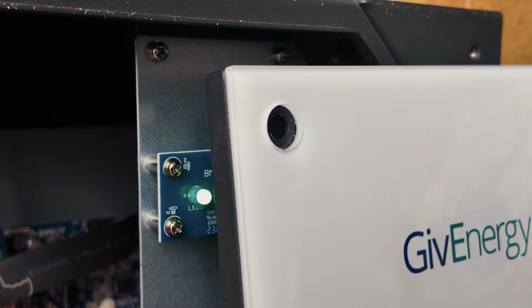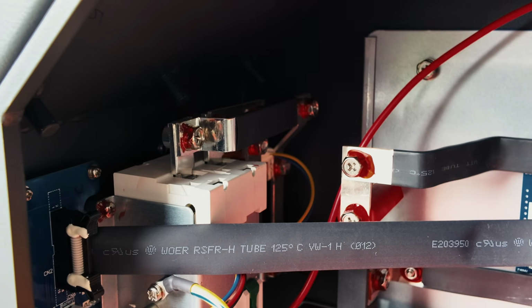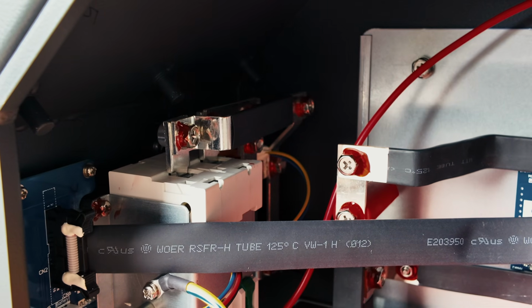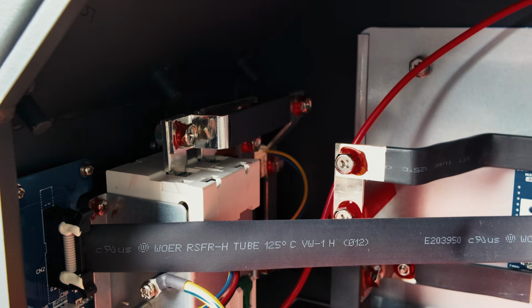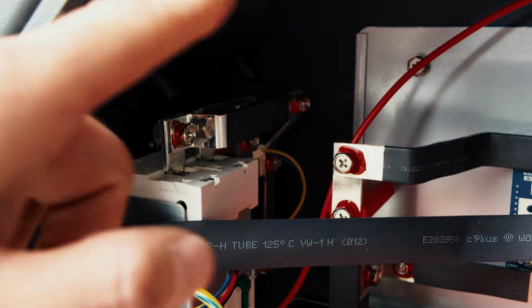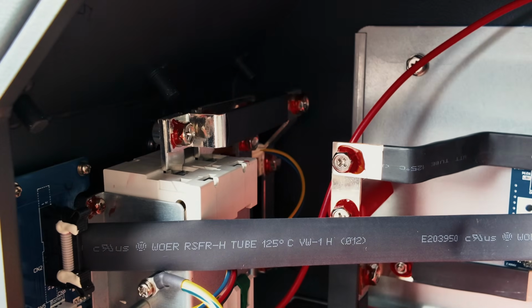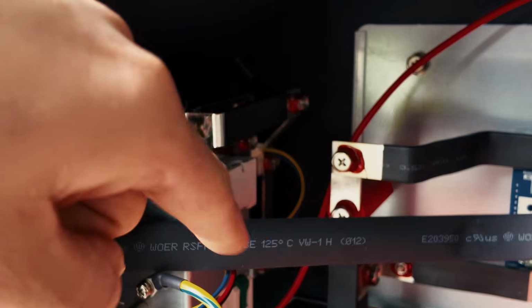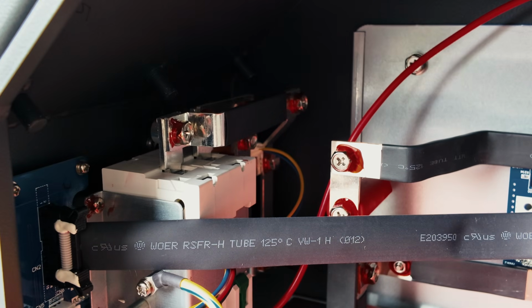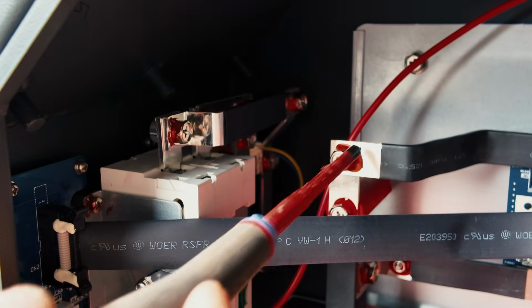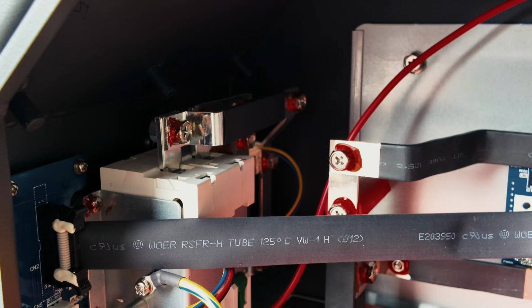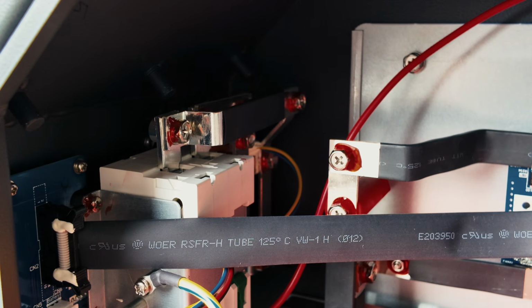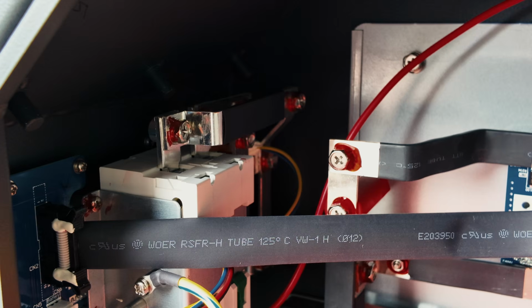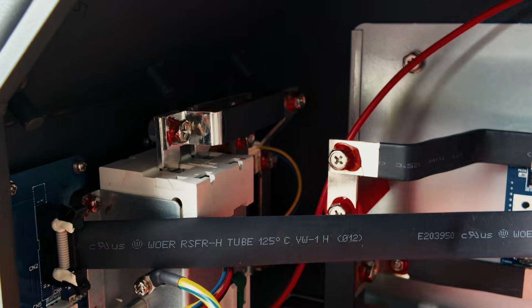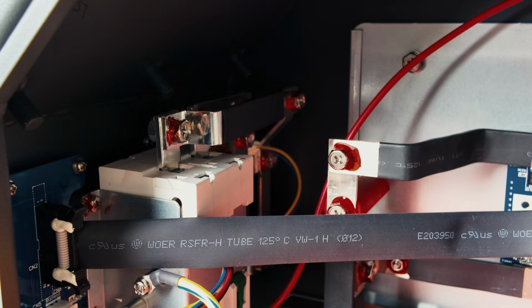I suspect it may well be a problem with the MCB. Right, there's the MCB. So we should have voltage on the bottom and voltage on the top. Top is our outgoing, so that's supplying the inverter, and bottom is from the battery cells just down here. I've got this screwdriver. Obviously this terminal bar here is our supply side from the battery, so I'm going to check voltage on those, see what we get. It should be around 48 volts. If any of this is low, we'll switch the isolator off and double check a couple of things, but it might be the cells need charging themselves.